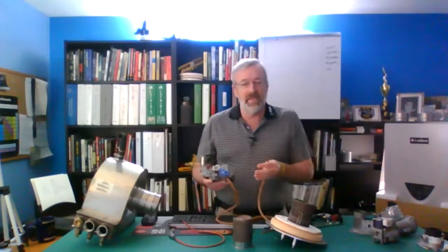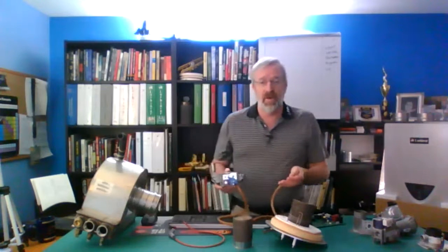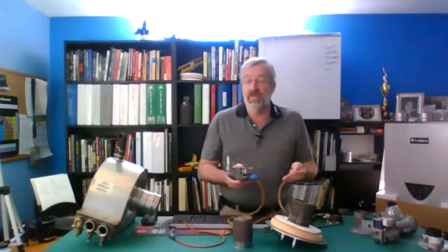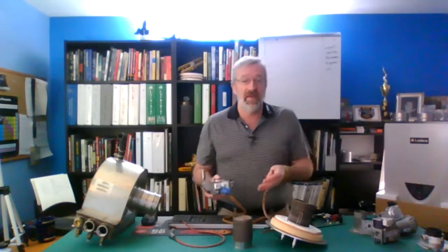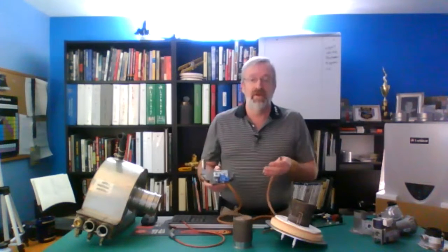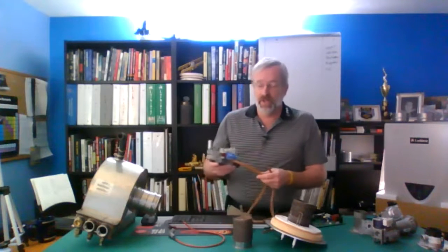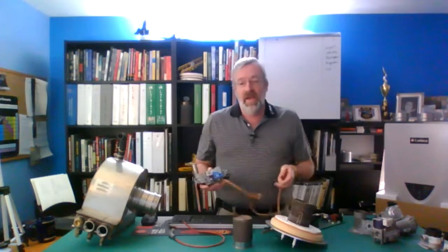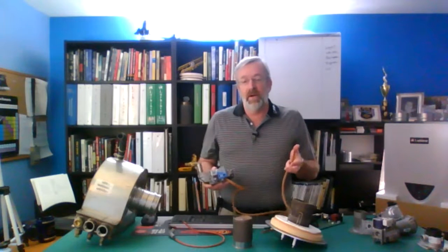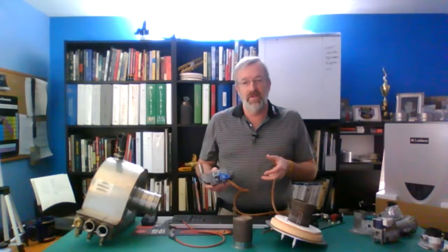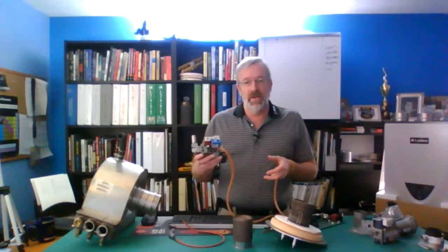And there are definitely some ways to eliminate some things. You've got a boiler that's been in a couple of years, gas pressure's never been a problem, and all of a sudden you've got a 6-inch drop in gas pressure. Hey, let's go out to that meter quickly and just see, do I have a meter hanging up? It's a good cause of that sometimes. If on my manometer, I go from 8 inches and I stay at 8 inches, there's a pretty good chance my gas valve didn't open.